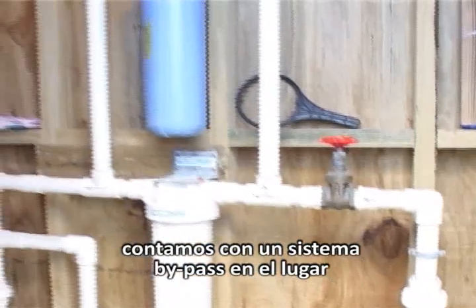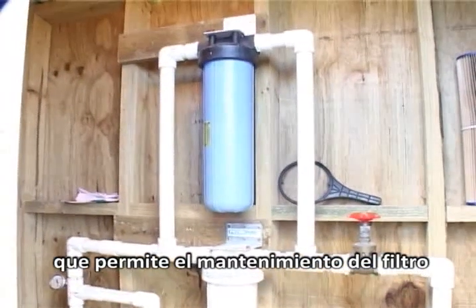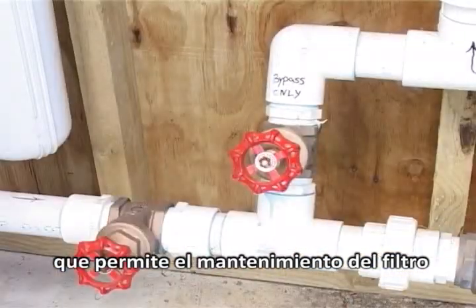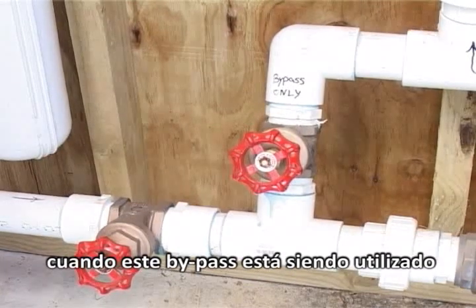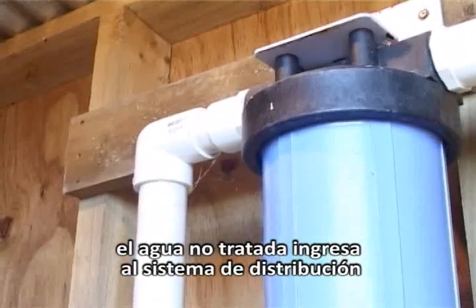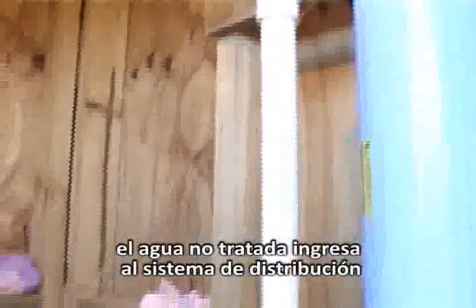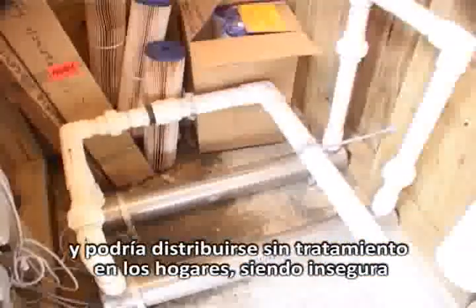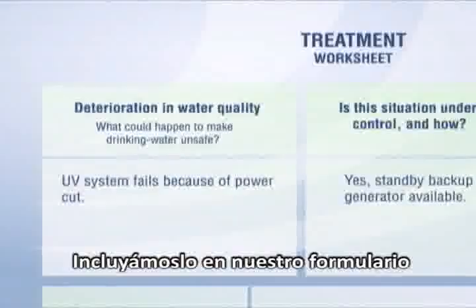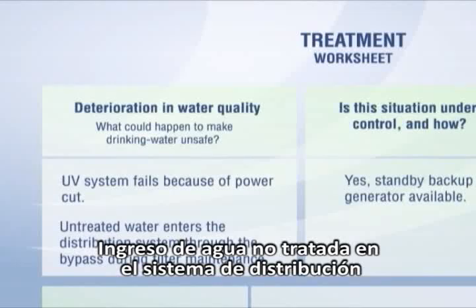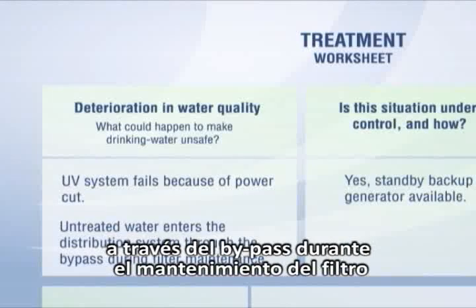Now in this case, we have a bypass system in place to allow for maintenance of the filter. However, when this bypass is in use, untreated water enters the distribution system and water will be sent to homes untreated. This is then unsafe, and let's add that to our worksheet. Untreated water enters the distribution system through the bypass during filter maintenance.